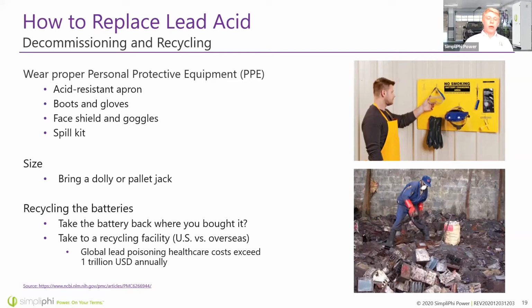Another point when removing lead acid batteries is that they're quite large, and you're definitely going to need a dolly or pallet jack if it's a big system. This is a consideration to make, especially off grid, before you even install these batteries - how are you going to remove them? In some remote scenarios, it's nearly impossible to get these batteries in and out of the site.